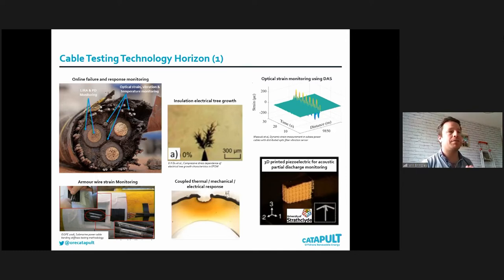We're also looking at the interface or the insulation with electrical and thermal stresses. So through some academic projects, we're testing a cable on a test rig, applying a current with a known electrical tree defect and seeing how that grows with and without strain. Particularly of interest for high voltage cables where we don't really know how they perform dynamically. And then on the bottom right there, quite a novel technology, looking at 3D printing piezoelectric sensors to pick up partial discharge, insulation problems at low cost and potentially high sensitivity as well. So there's lots of things that we can test on the test rig.